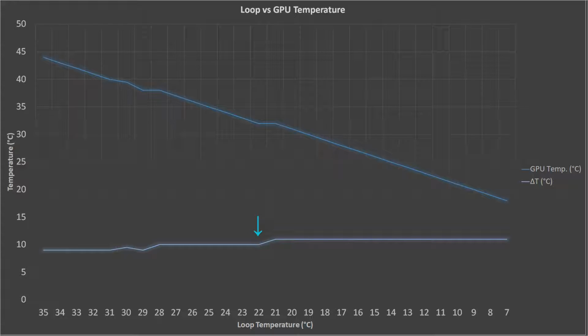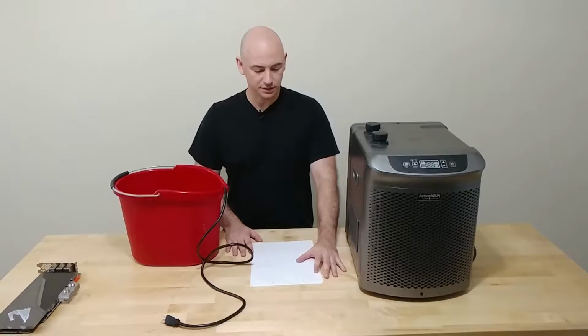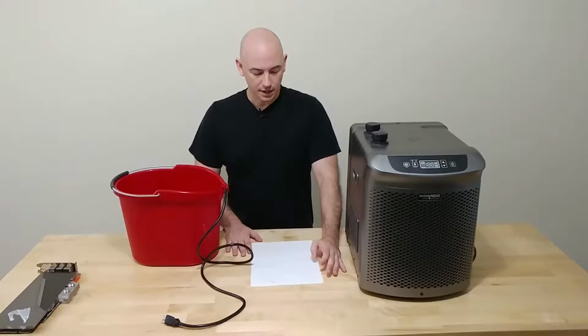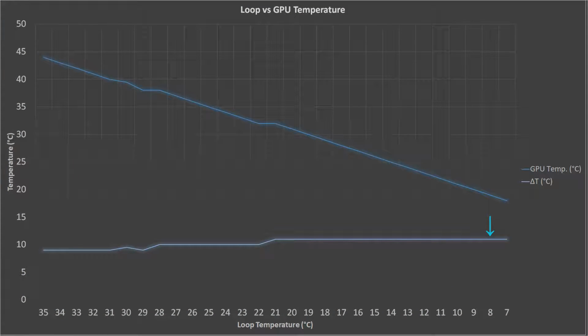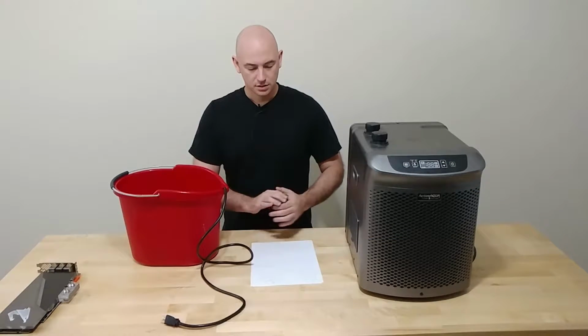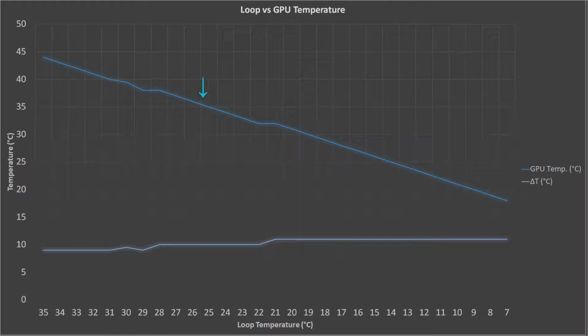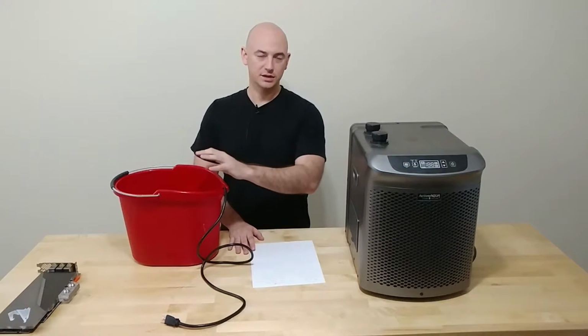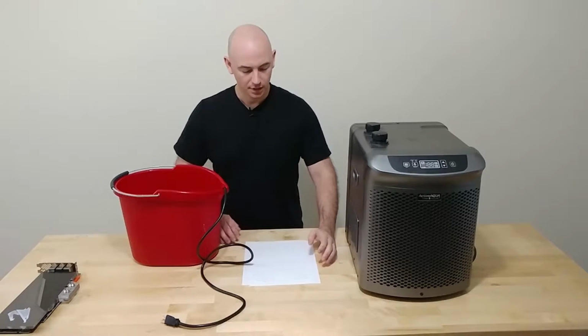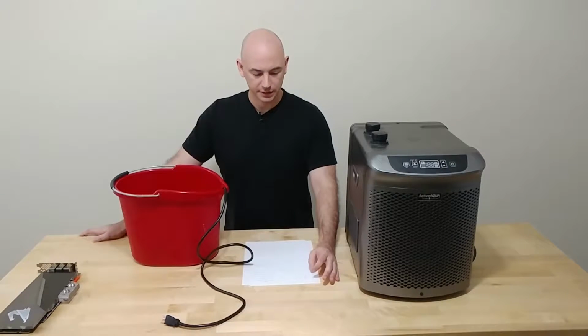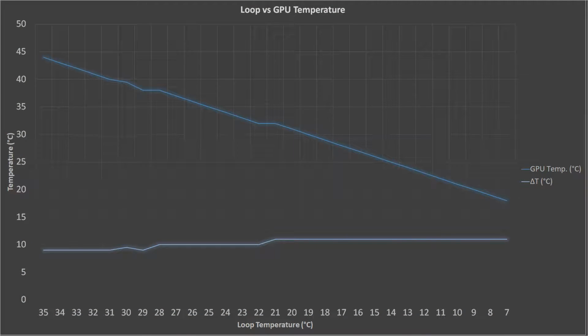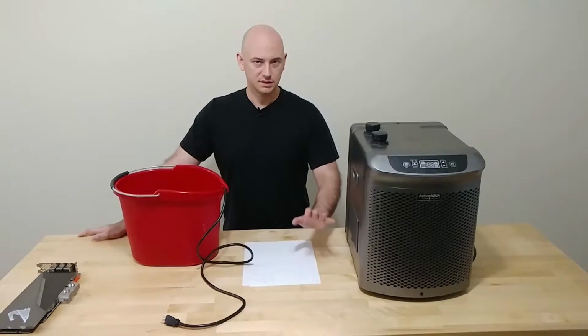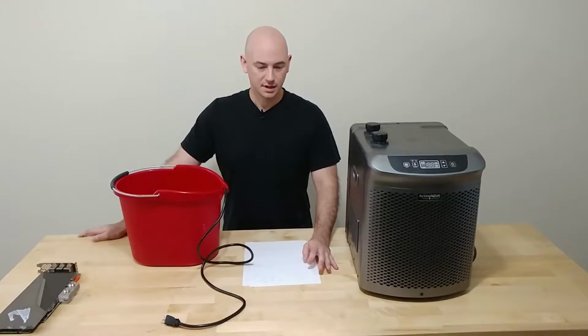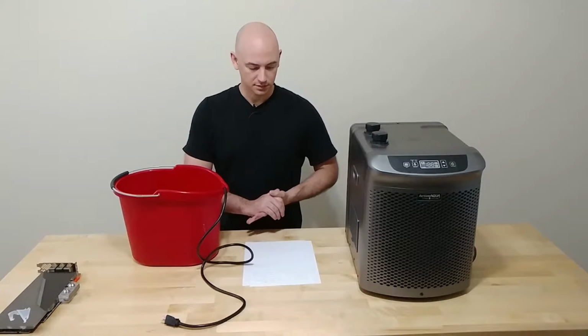Moving down to 22 degrees on the chiller, we started to see a 10 degree delta. So 22 degrees on the chiller, 32 on the GPU. And then all the way down to 8 degrees fluid in the loop. So right off the chiller, the GPU was reading 19 degrees Celsius. So that's an 11 degree delta. There were a few steps in the delta. It was fairly linear, and it stayed at about 1 degree of water per degree change in temperature of the GPU. But an interesting thing here, it wasn't exactly 1 degree, because at 35 degrees we were seeing a delta T of 9, and down at 7 and 8 degrees we're seeing a delta T of 11. So it was less thermally efficient at the lower temperatures, because we were seeing a greater disparity between the high side and the low side.